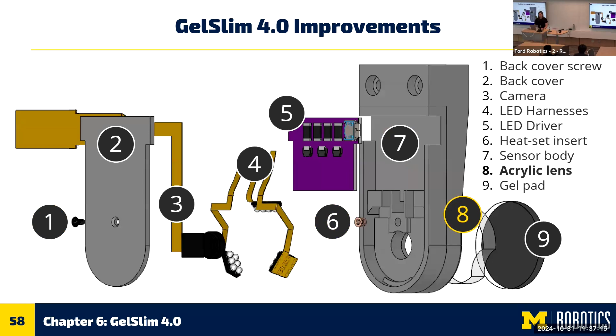To consolidate the sensor, I redesigned the sensor body to be one single component, which eliminates 3 heat set inserts from the original design that were quite difficult to place. Additionally, I reduced the number of press fits of the sensor body to simplify manufacturing. I also made it easier to integrate the camera and lock it in place inside the sensor body by securing it with fasteners rather than a press fit. Finally, I revised the lens of the sensor to reduce its cost from $50 to 13 cents, allowing it to be treated as a consumable component.